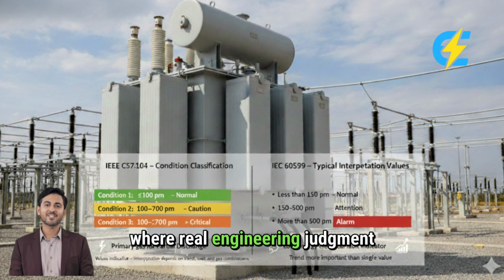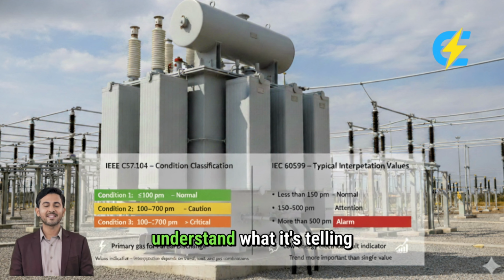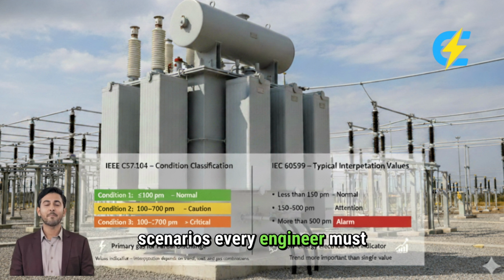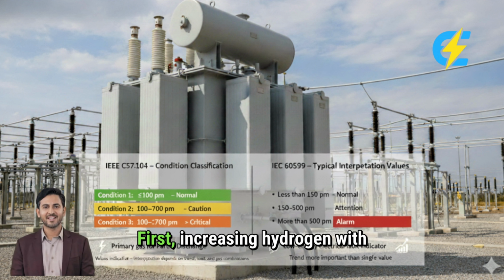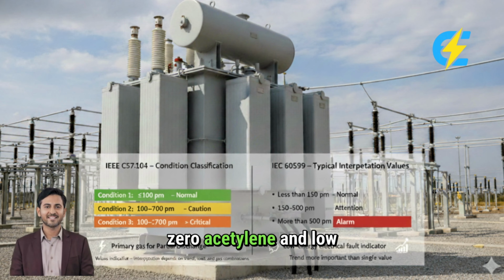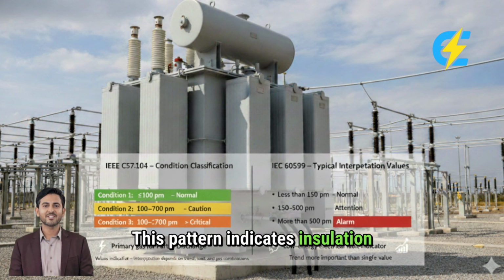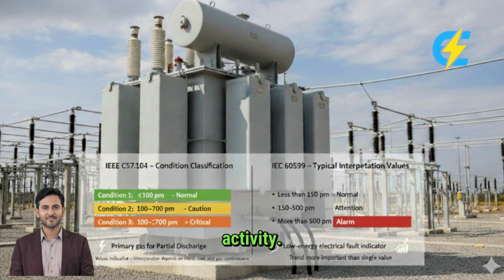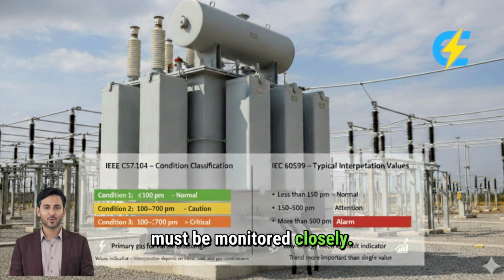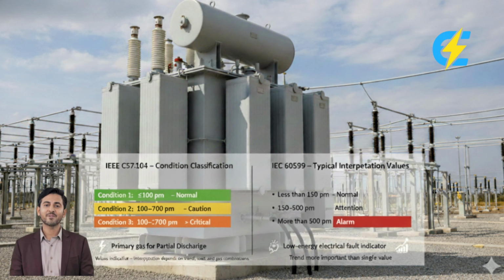But here's where real engineering judgment starts. When hydrogen begins to rise, you need to understand what it's telling you. There are two critical scenarios every engineer must recognize. First, increasing hydrogen with zero acetylene and low ethylene. This pattern indicates insulation stress or partial discharge activity. It's not an immediate shutdown condition, but it must be monitored closely. The transformer is telling you that something has started, but it's still early.